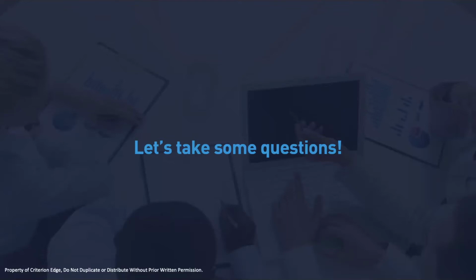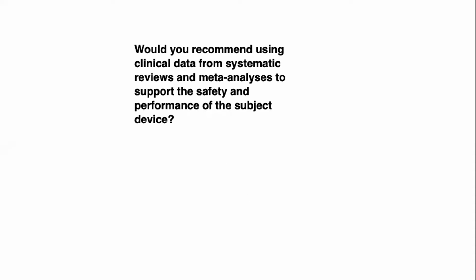Our first question is, would you recommend using clinical data from systematic reviews and meta-analyses to support the safety and performance of the subject device? Well, that's a good question, and it's a little bit of a trick question. Not for supporting the safety and performance of the subject device, primarily because of that last clause.